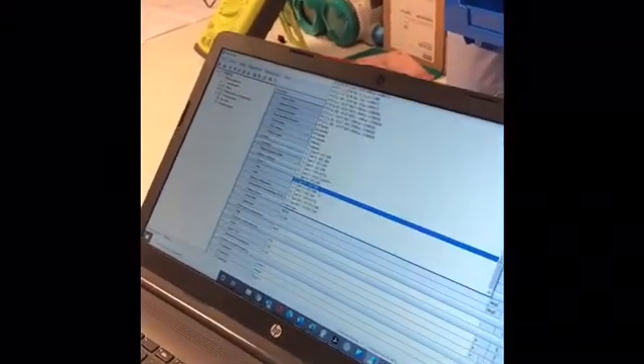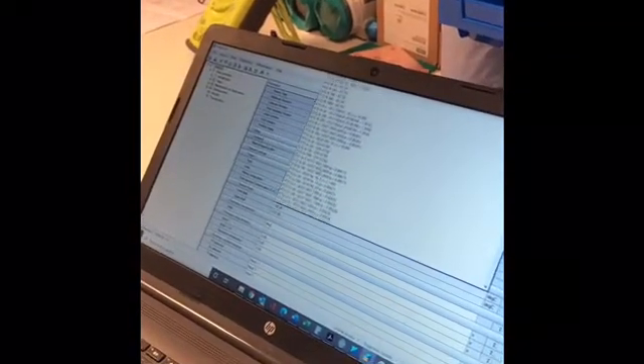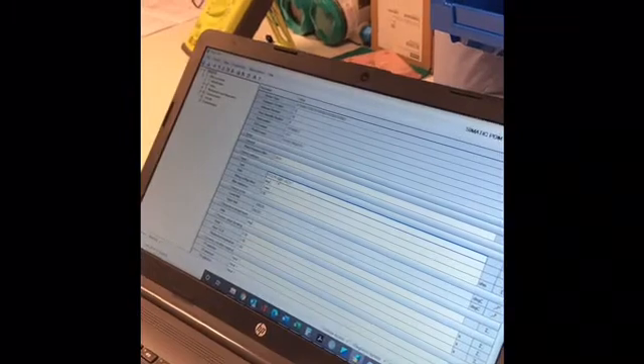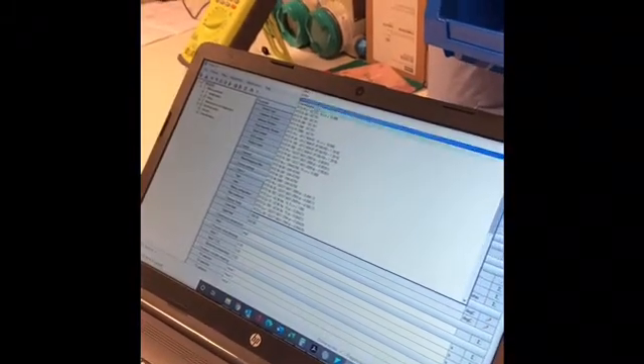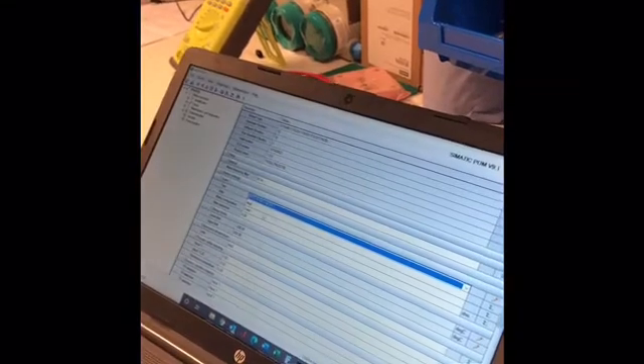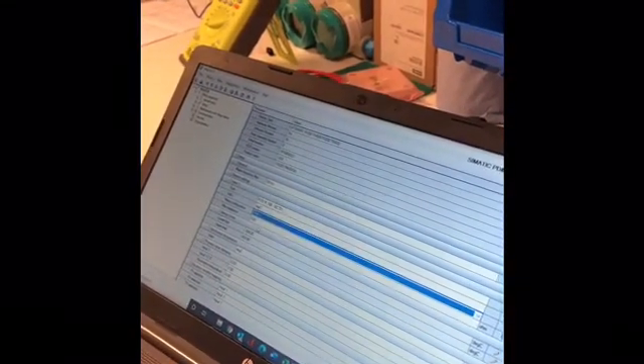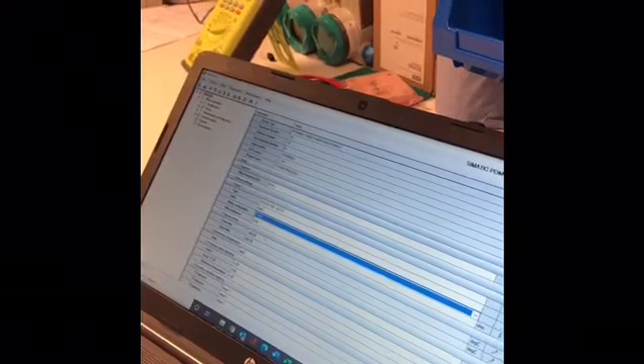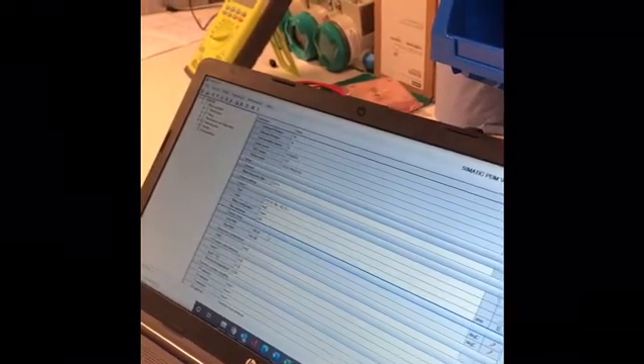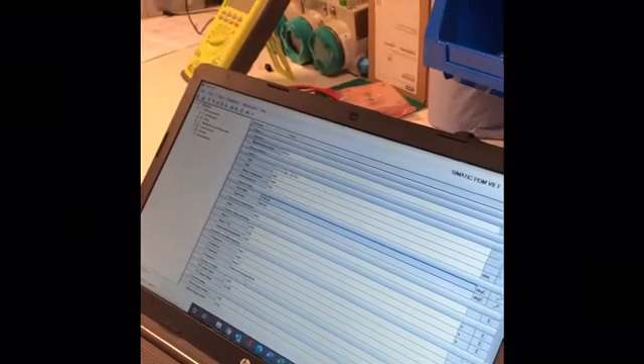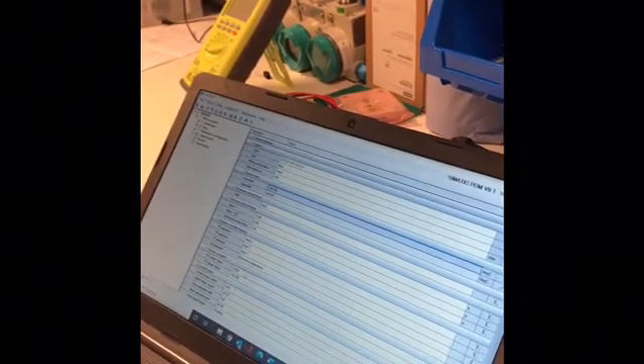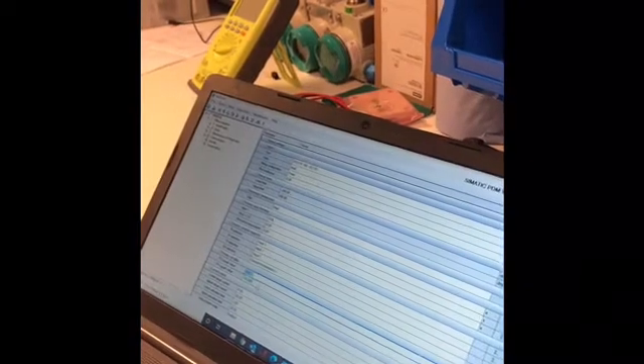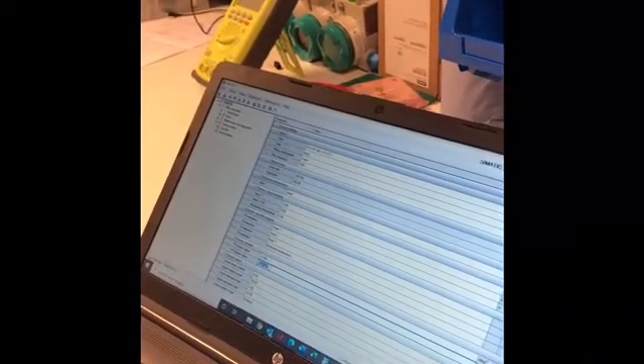And then you would come down and you could change the type if you wanted to set to a PT100. So a PT100, let's make that a three wire. And we've got our upper and lower range values. So let's make this one 50 degrees.